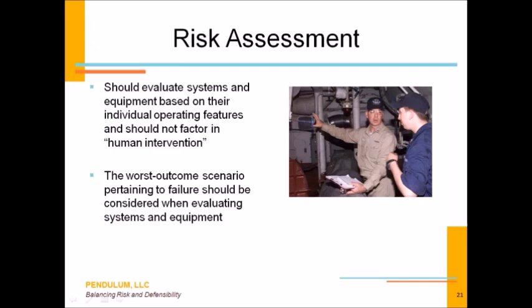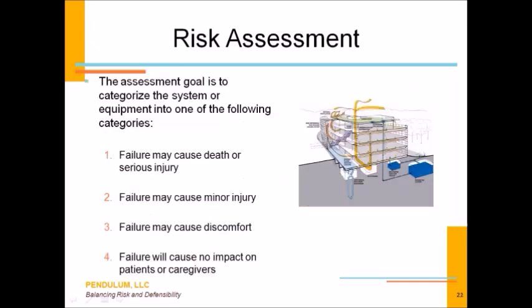Let's talk about your electrical system. We're talking about failure of your municipal electrical feed that's coming into your healthcare facility, as well as failure of any redundancies or backups. So we're talking about your emergency generator. You've got to assess the risk of catastrophic failure without any human intervention of a system within your facility. So that's how you assess the risk. And when you're looking at that catastrophic failure, you're going to categorize that risk into four specific categories.